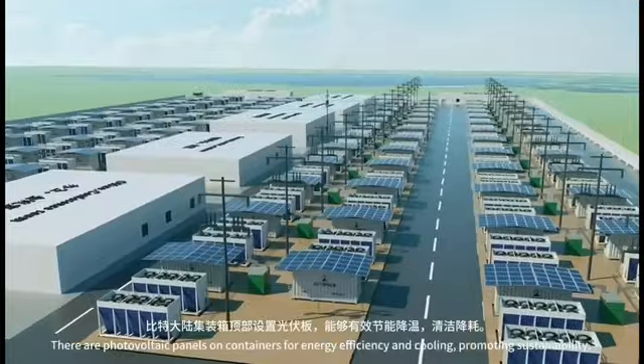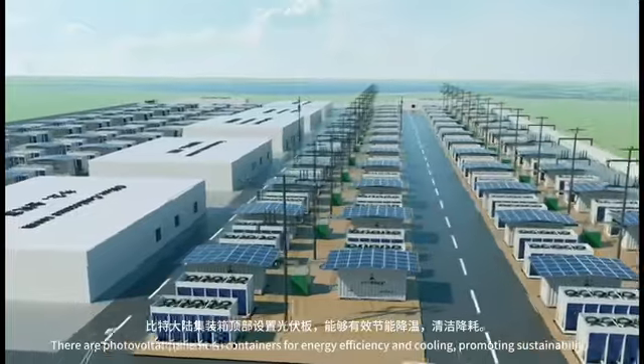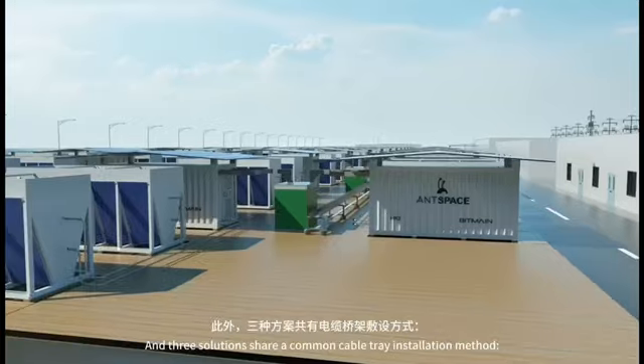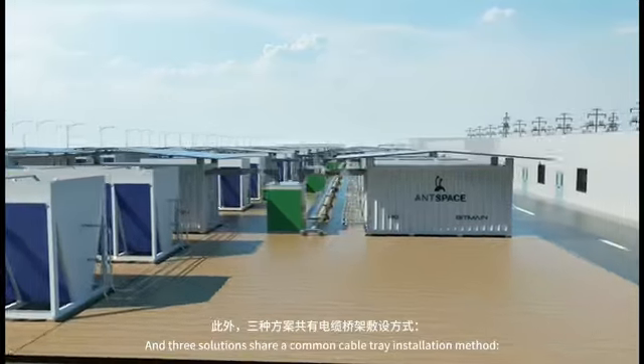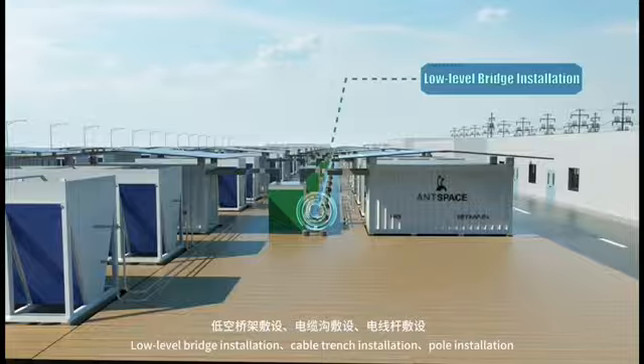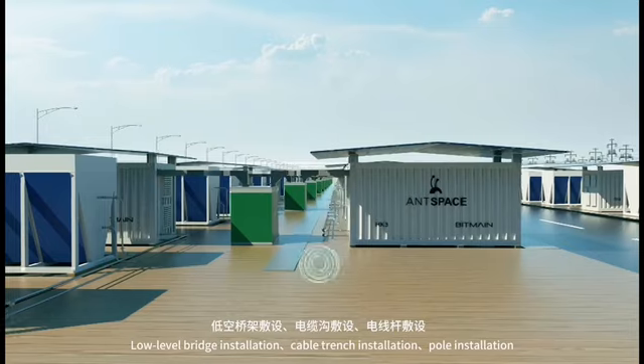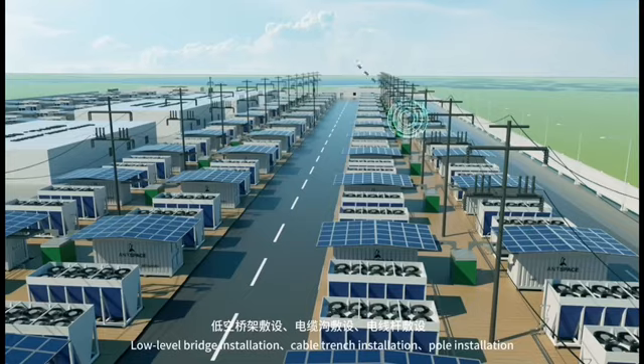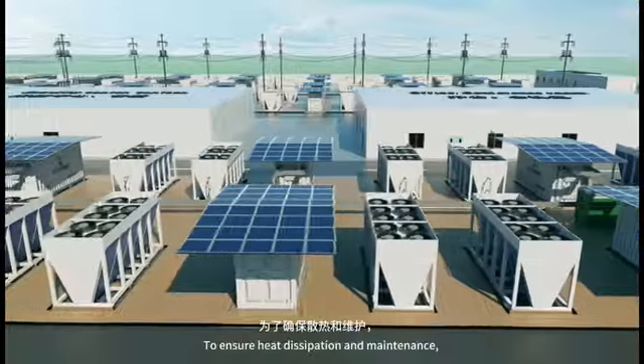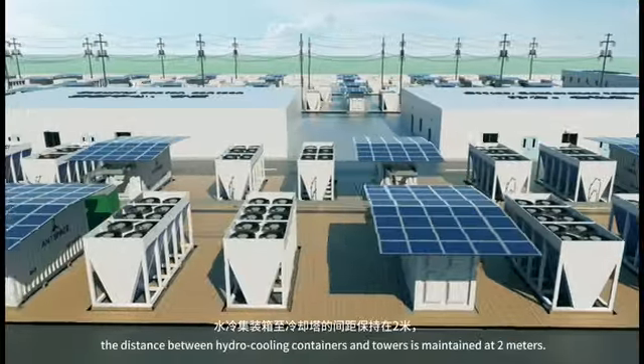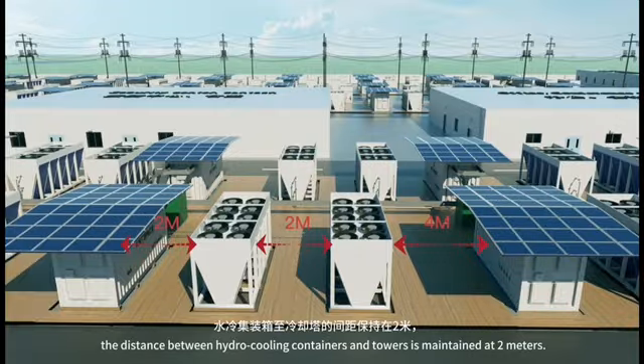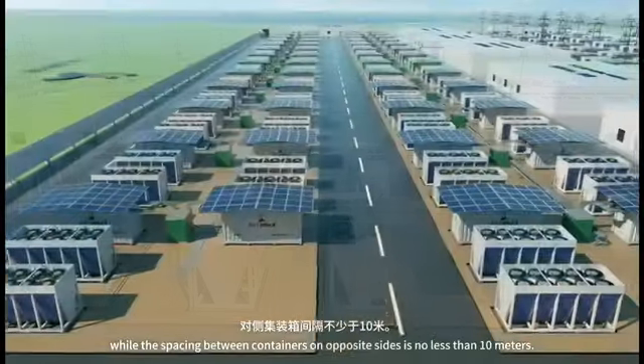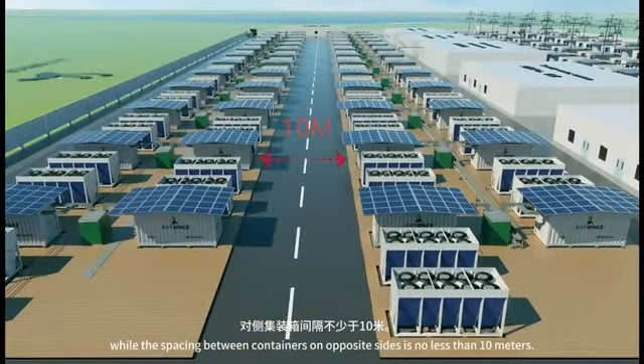There are photovoltaic panels on containers for energy efficiency and cooling, promoting sustainability. And the 3 solutions share a common cable tray installation method. Low-level bridge installation, cable trench installation, pole installation. To ensure heat dissipation and maintenance, the distance between hydro-cooling containers and towers is maintained at 2 meters, while the spacing between containers on opposite sides is no less than 10 meters.